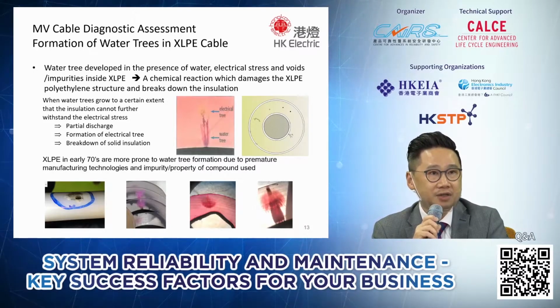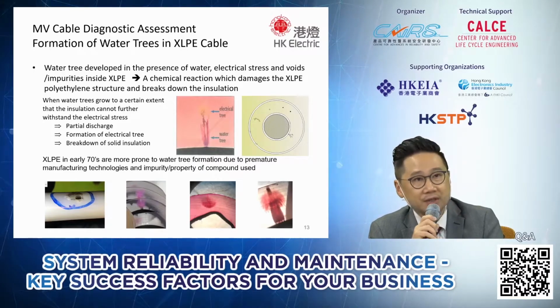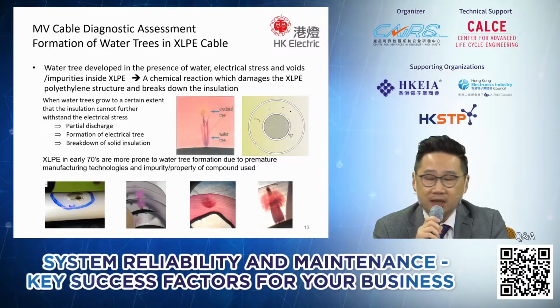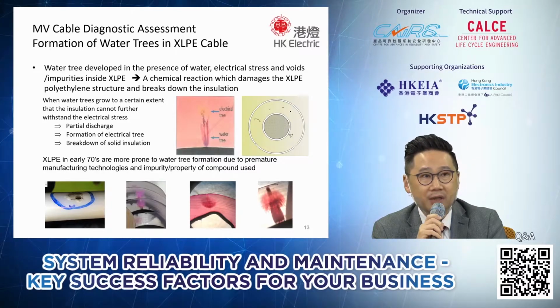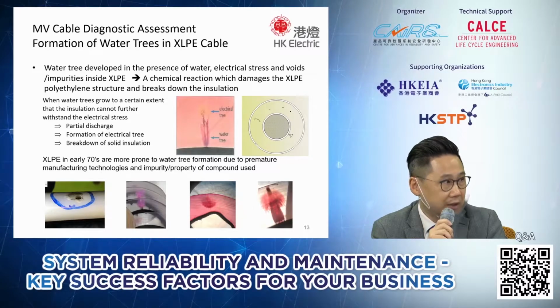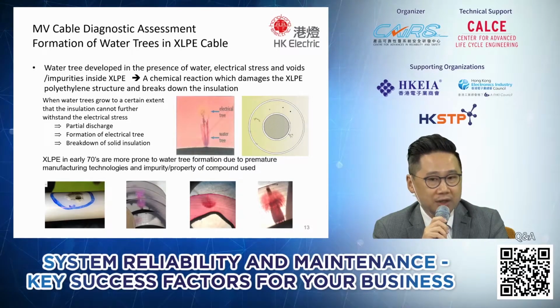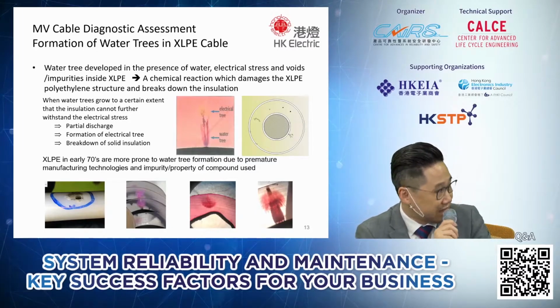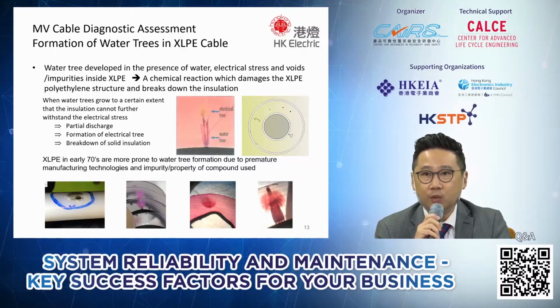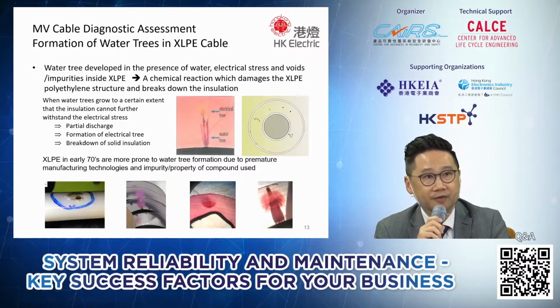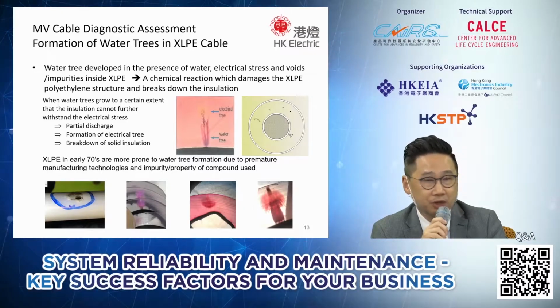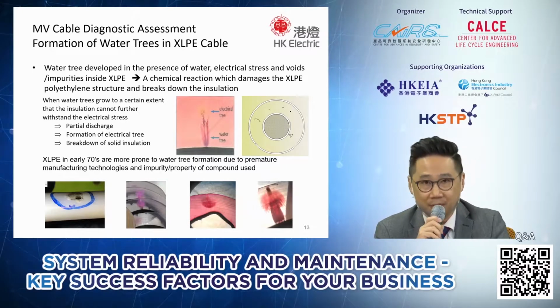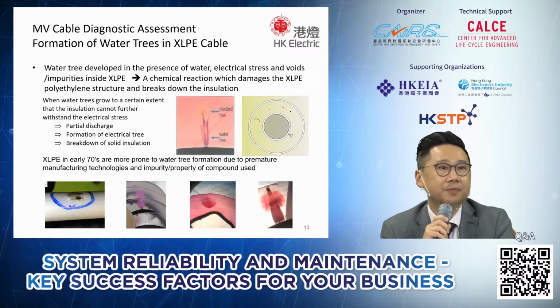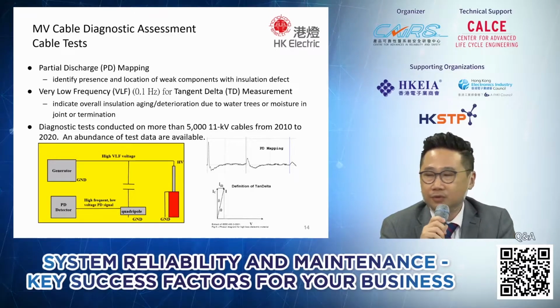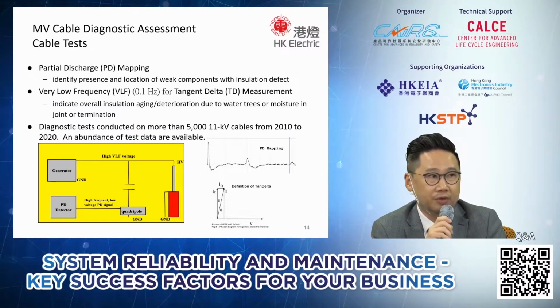We found that the insulation has some impurities and voids inside the plastic. As time goes on, and if there is water around, it may develop into what we call a water tree. Water is a pretty good conductor, and if it develops into a water tree, it will degrade the insulation. As time goes on, it may become a weak point in the insulation, and partial discharge may happen in this area. If it happens, the cable will be damaged and burnt. So we have to find ways to predict when a cable will become faulty.